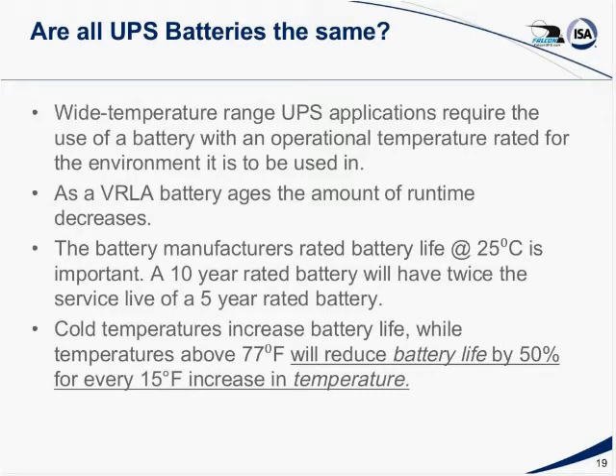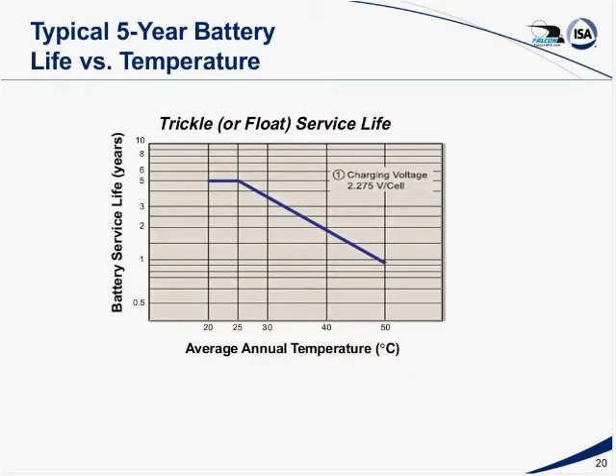In fact, battery manufacturers typically rate their battery life at 25 C or 77 degrees F. When you increase that above 77 F, the battery life will be reduced by 50% for every 15 degrees F increase in temperature. Well, could you show us what a 5-year battery typically looks like? Sure. This is a manufacturer's data sheet portion for a 5-year rated battery. If you look at 25C, there is a 5-year life. But when you go to 50C, you're looking at about a 9-month life.